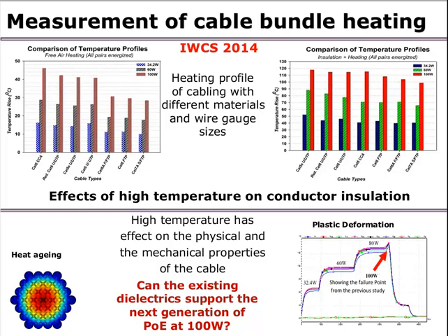As shown on this slide, we tested both shielded and unshielded twisted pair cabling under two installation environments. We considered bundled cables installed in ventilated spaces, which we called free air heating here. We also tested cable bundles installed in unventilated spaces, such as cable bundles installed in some pathway systems, such as conduits, and at the same time kept behind wall, ceiling spaces, or thermally insulated environments in general.